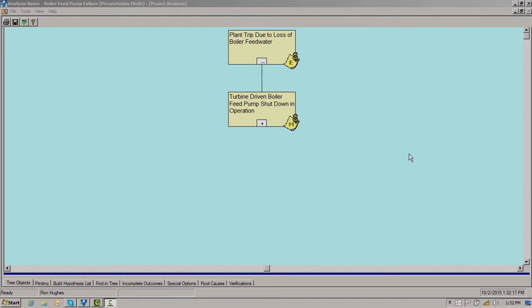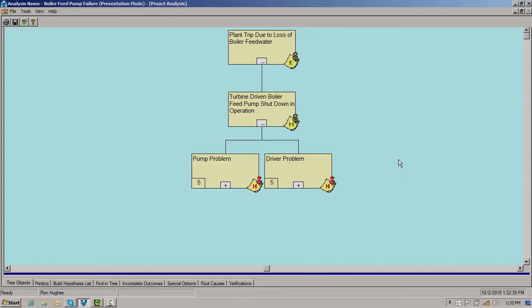Now let's look at how we analyze this problem. The failure event, or the reason why we're taking action, is the plant trip due to loss of boiler feed water. The failure mode is the turbine-driven boiler feed pump shutting down in operation. We ask ourselves how the pump could shut down in operation and come up with two possibilities: either a pump problem or a driver problem.